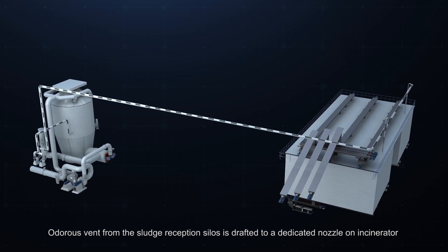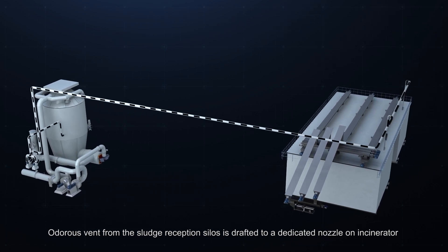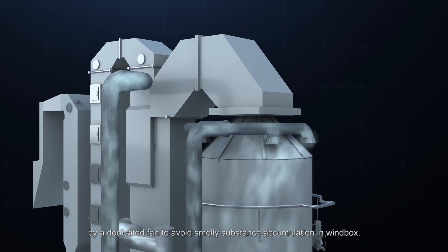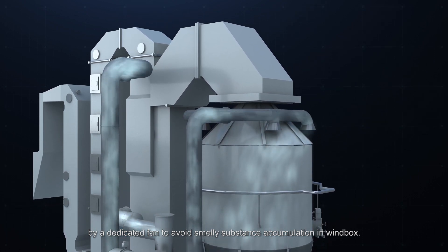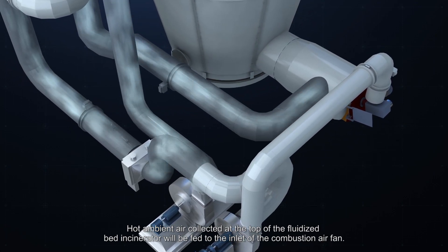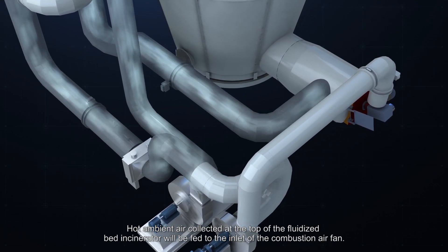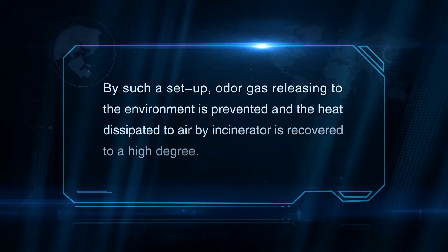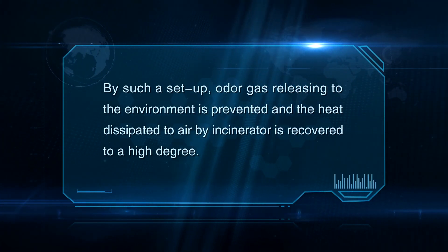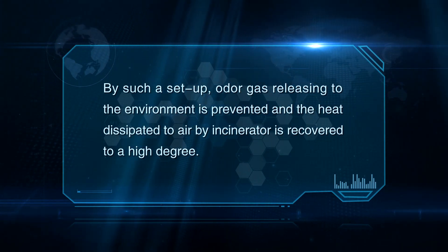Odorous vent from the sludge reception silos is drafted to a dedicated nozzle on incinerator by a dedicated fan to avoid smelly substance accumulation in windbox. Hot ambient air collected at the top of the fluidized bed incinerator will be fed to the inlet of the combustion air fan. By such a setup, odor gas releasing to the environment is prevented and the heat dissipated to air by incinerator is recovered to a high degree.